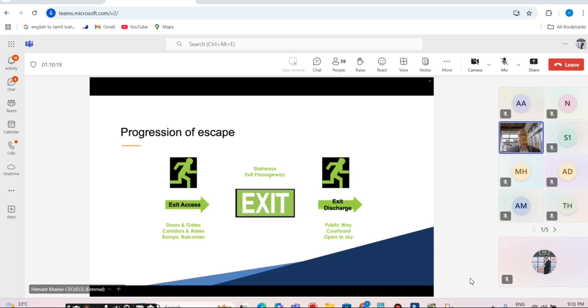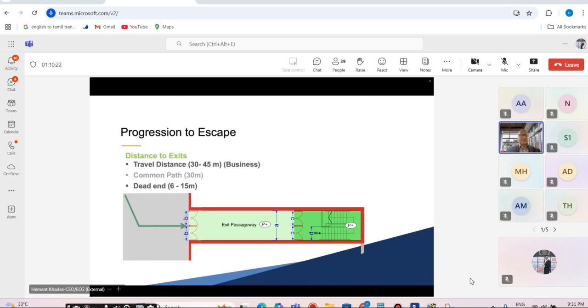Very importantly, people must be aware of the criteria stipulated in the codes and standards. Every code and standard has different travel distances based on the occupancy. So travel distance essentially is the pathway, which is a combination of your common path to reach the fire exit. So the code always regulates your travel distance, and your common path and dead end both. Dead end is very important, and we have to see that it doesn't exist in your project.